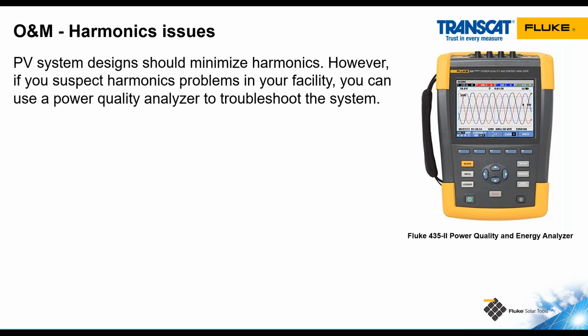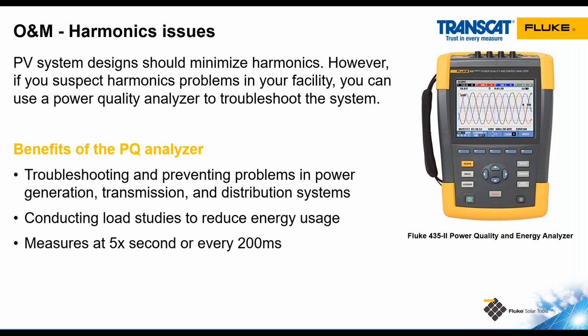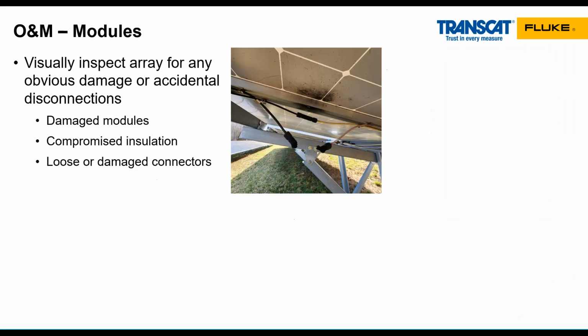We have a range of power quality meters that can be used to identify harmonics issues. Another interesting thing with some of our power quality meters is they can be used to conduct load studies. So we can put the power quality meter in place, we can leave it there for a time, we can see how much power and energy a load in a building is using, and we can use that data to properly size energy storage systems for backup use cases. So that's a nice feature of some of those power quality meters.